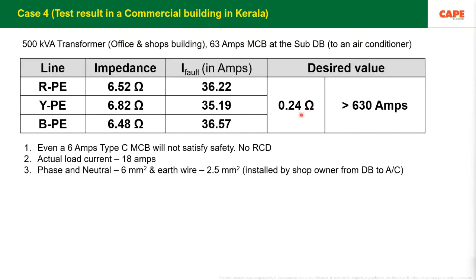The result of this particular study is that even if he has a 6 amps MCB, type C MCB, a 6 amps MCB cannot trip in this situation. So the installation was so bad. The actual load current was 18 amps, and for the phase and neutral he has used 6 millimeter square, and for the earth wire he has used a 2.5 square mm wire.